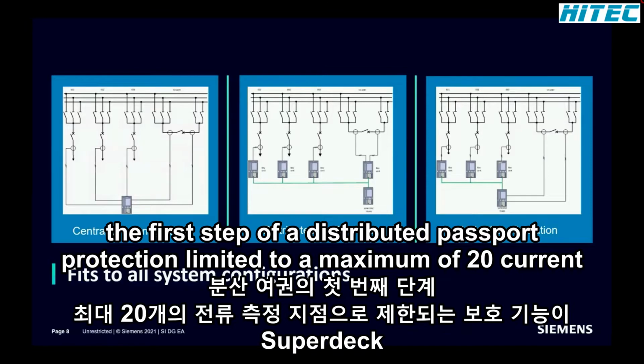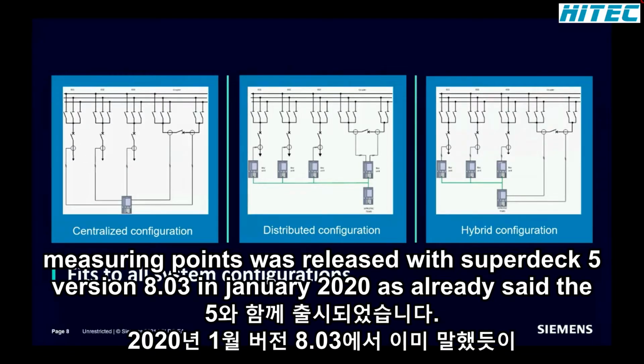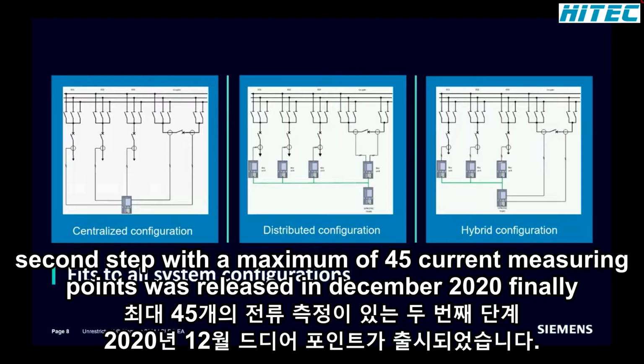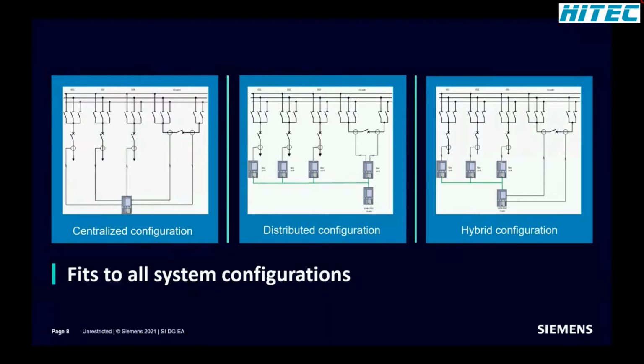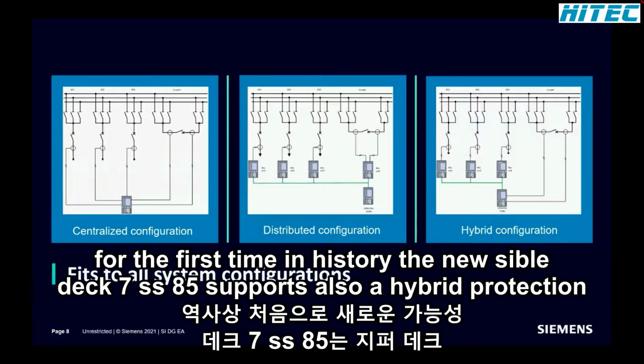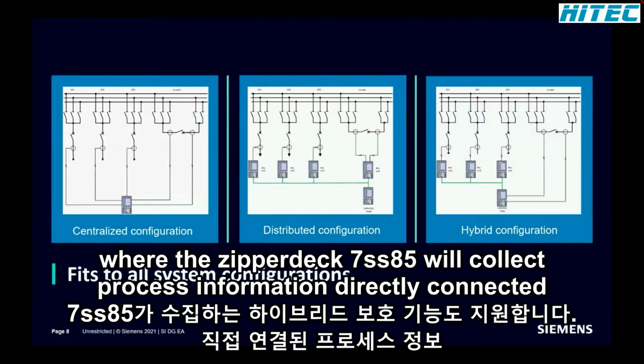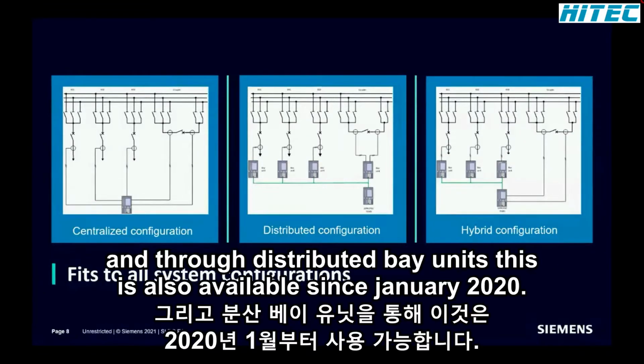The first step of a distributed busbar protection, limited to a maximum of 20 current measuring points, was released with SIPROTEC 5 version 8.03 in January 2020. As already said, the second step with a maximum of 45 current measuring points was released in December 2020. Finally, for the first time in history, the new SIPROTEC 7SS85 also supports a hybrid protection, where the SIPROTEC 7SS85 collects process information directly connected and through distributed bay units. This is also available since January 2020.